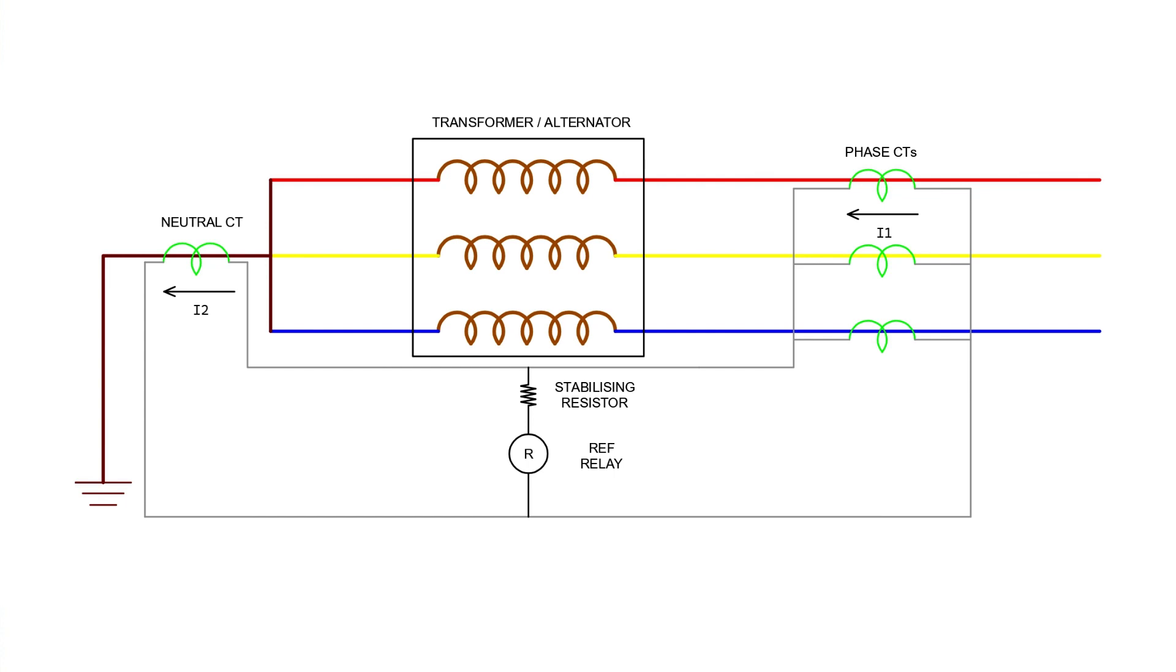In restricted earth fault scheme, the common terminals of phase CTs are connected to the secondary of neutral CT in such a manner that secondary unbalanced current of phase CTs and the secondary current of neutral CT will oppose each other. If these both currents are equal in amplitude, there will not be any resultant current circulates through the said closed path.